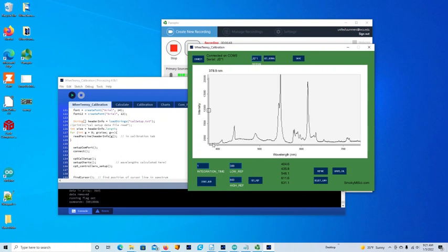Let's just make sure that's not an anomaly, which it kind of is. 389 looks like a really nice number there, right? Okay, so that is our low value, our low reference. Now we have to set the high reference.